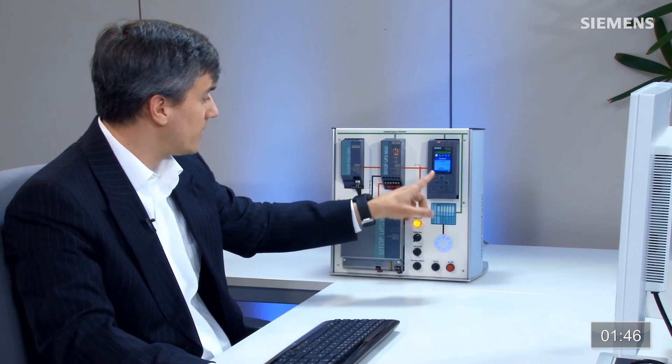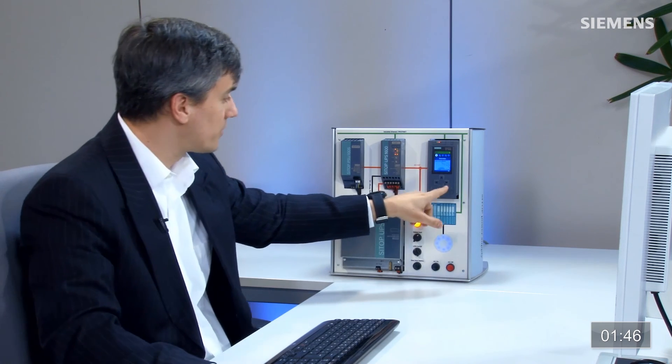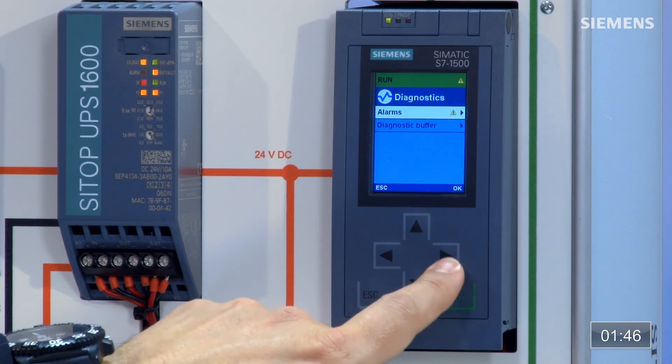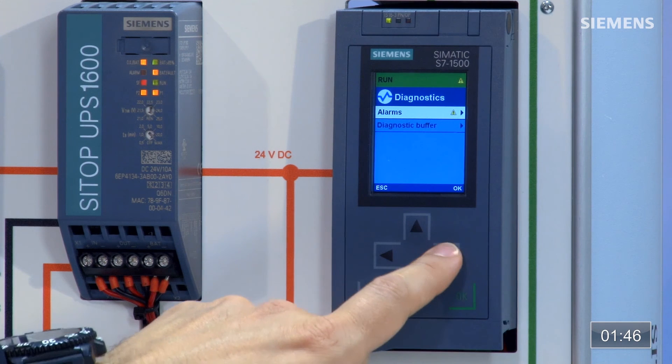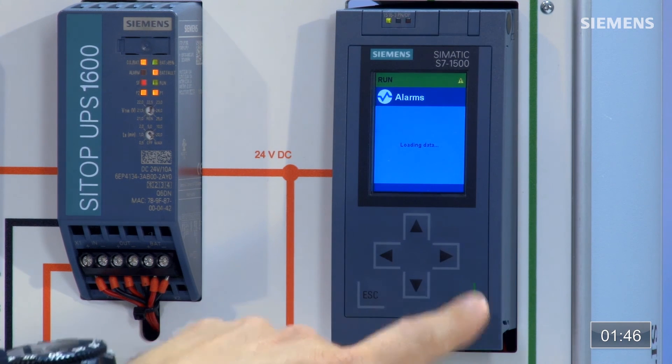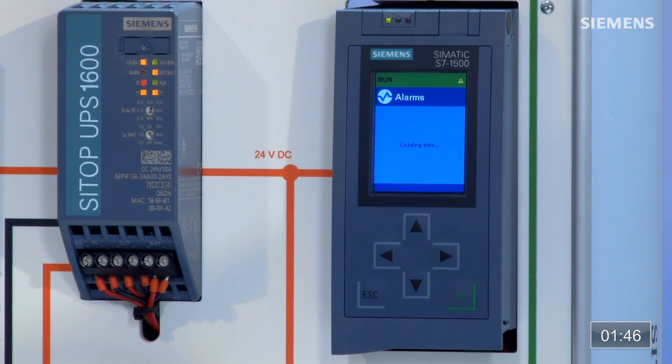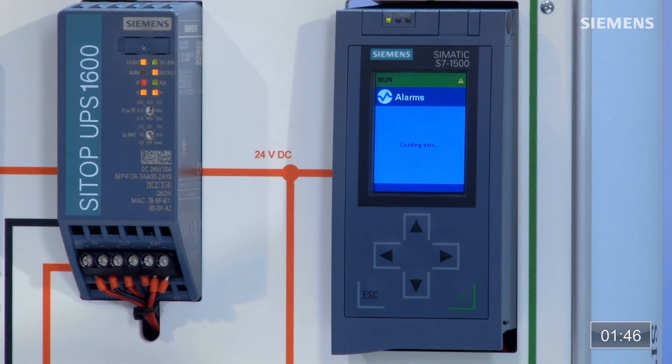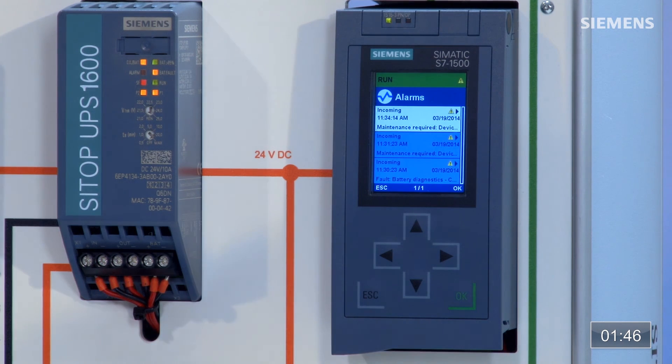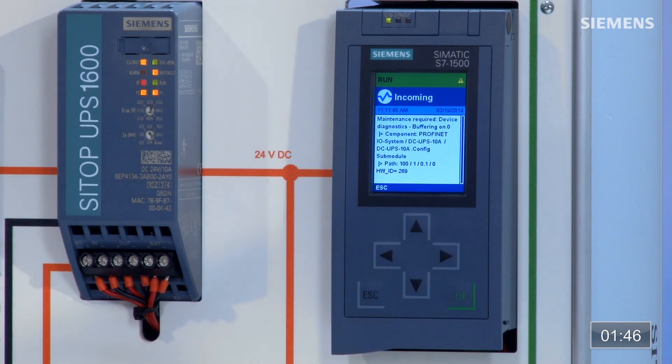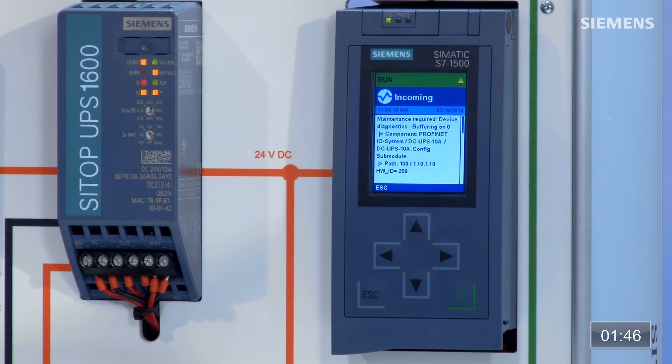So the next thing I'd like to do is actually turn the AC off and let's use the actual 1500 to diagnose this. Let's go over to our alarms, click OK. It's going to update and look for everything in the system buffer. You can see we have a maintenance here and even the 1500 controller knows that we've gone into buffering mode.